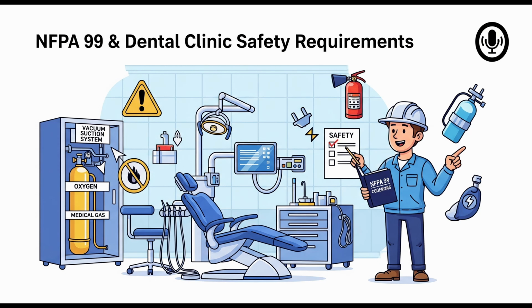Let's switch gears slightly. What about the gas cylinders themselves? The oxygen tanks, the nitrous tanks. How does NFPA 99 say they need to be stored in a dental clinic? Storage. Yes. Chapter 11 is the main reference for cylinder storage, handling, and use. And Section 15.4.2.4 adds specifics for Category 3 facilities. The rules are all about preventing hazards: fire, leaks, physical impacts.